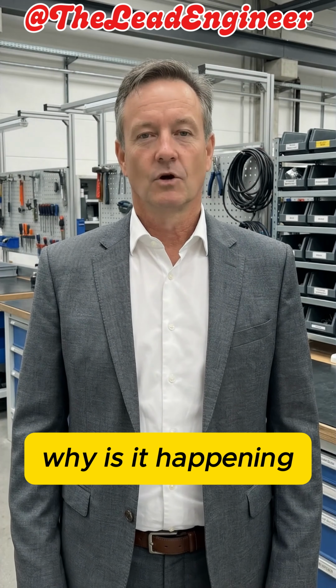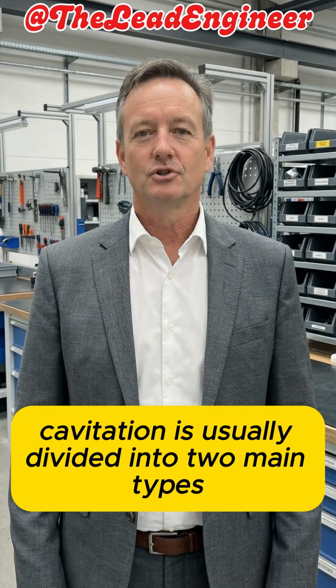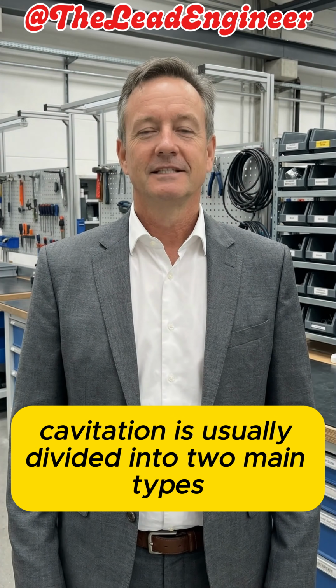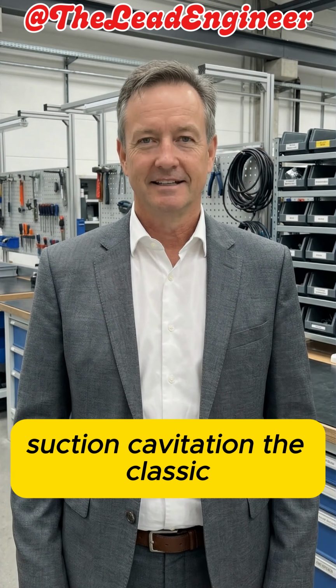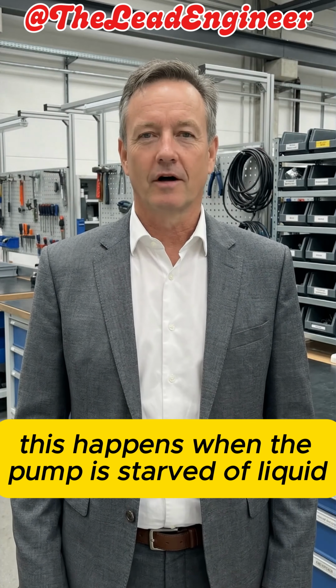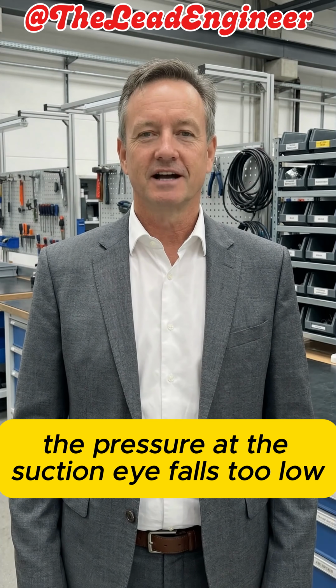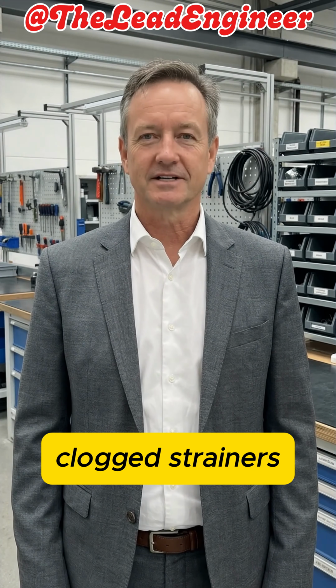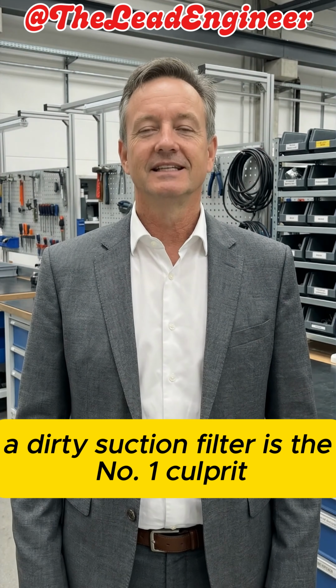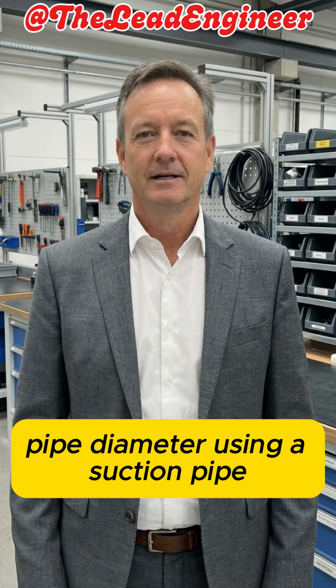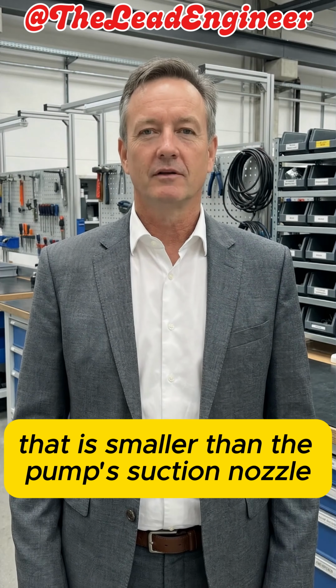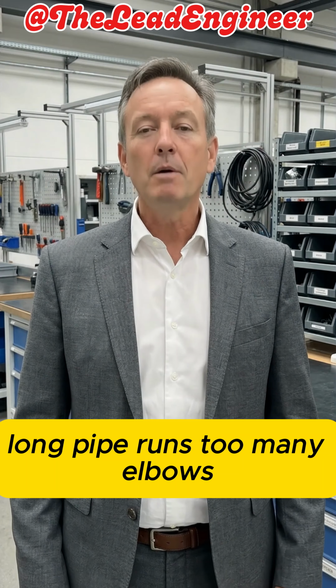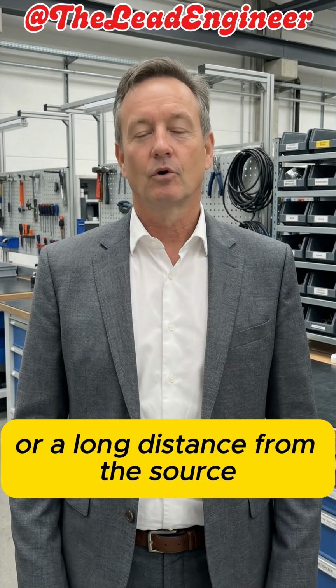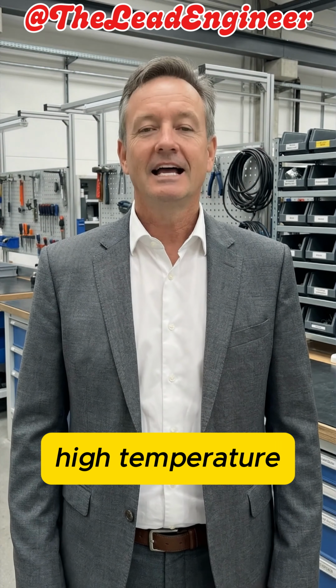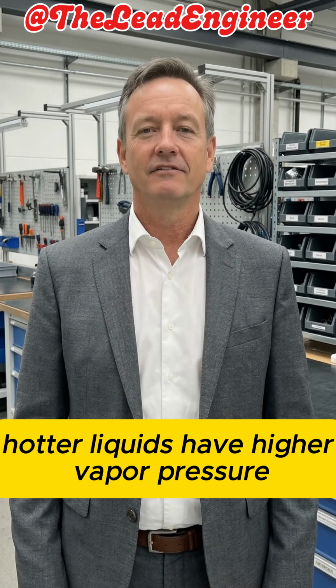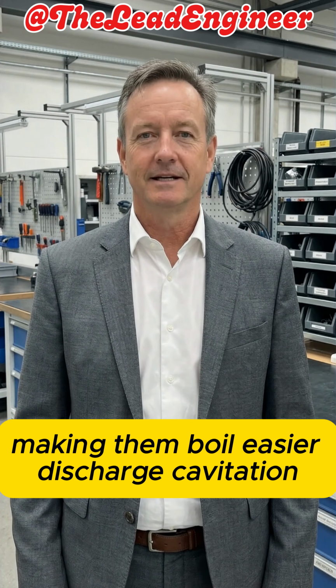2. The causes. Why is it happening? Cavitation is usually divided into two main types. Suction cavitation, the classic. This happens when the pump is starved of liquid. The pressure at the suction eye falls too low. Clogged strainers. A dirty suction filter is the #1 culprit. Pipe diameter. Using a suction pipe that is smaller than the pump's suction nozzle. Long pipe runs. Too many elbows or a long distance from the source. High temperature. Hotter liquids have higher vapor pressure, making them boil easier.